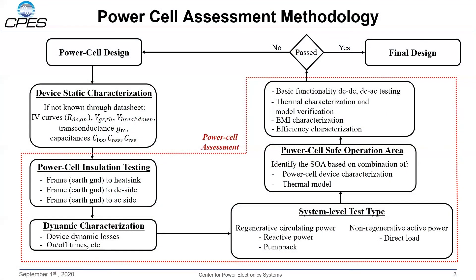The mission of the assessment methodology is to characterize the capabilities of the power cell as well as to explore its limitations. The first step is insulation testing, investigating maximum differential and common-mode voltage insulation capabilities of the power cell. This work was introduced by USU and Joshua Stewart in previous sections. Following that, the system level test type will be determined, after which the safe operating area will be defined. The SOA will be defined based on device characterization and a thermal model, so the thermal limit of the power cell at different conditions is known. Subsequently, a series of continuous tests are conducted to verify thermal management, dv/dt transient immunity, and efficiency performance. At the end, a decision will be made to determine whether the power cell design should be iterated. If passed, the power cell design is complete.